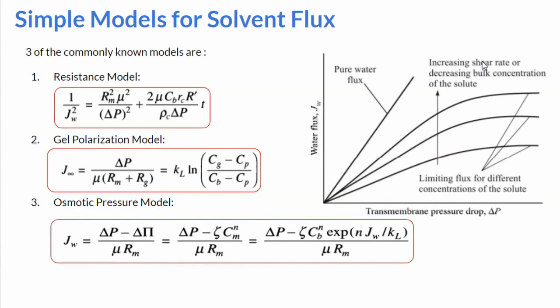Now we move to the topic of simple models for solvent flux. Pure water flux through a membrane linearly increases with applied pressure Δp. In the case of ultrafiltration, however, the increase of flux with pressure drop is slow and the flux levels off to a constant value at high Δp. This constant flux, which is independent of the resistance to flow offered by the membrane, is called the limiting flux. The limiting flux, as shown in the figure, increases with increasing cross-flow velocity or decreasing bulk concentration of the solute. Increasing cross-flow velocity enhances the mass transfer coefficient and reduces the solute concentration Cm in the vicinity of the membrane. A lower solute concentration in the bulk has a similar effect on the limiting flux.